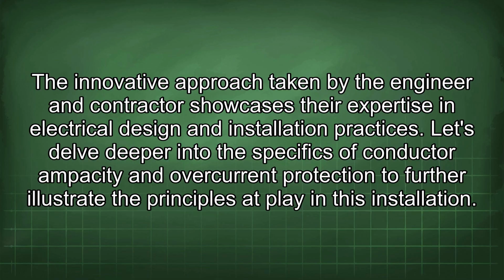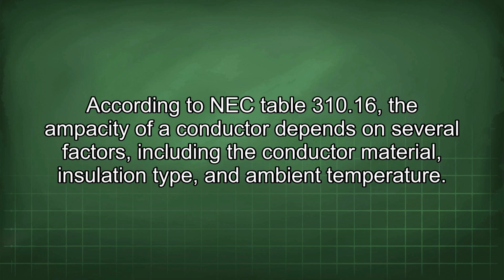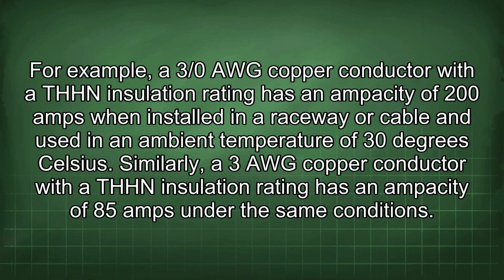Let's delve deeper into the specifics of conductor ampacity and overcurrent protection to further illustrate the principles at play in this installation. According to NEC Table 310.16, the ampacity of a conductor depends on several factors, including the conductor material, insulation type, and ambient temperature. For example, a 3/0 AWG copper conductor with a THHN insulation rating has an ampacity of 200 amps when installed in a raceway or cable and used in an ambient temperature of 30 degrees Celsius.